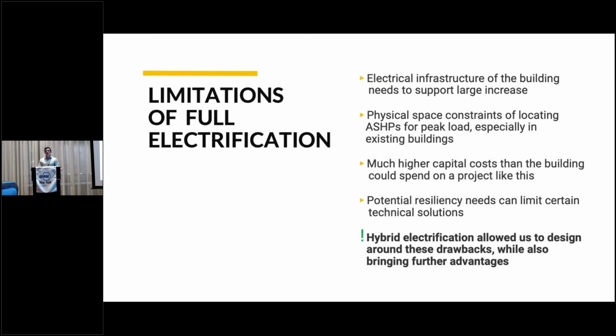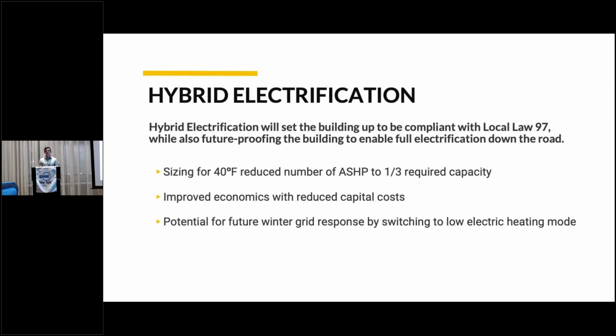So when we were looking at a hybrid electrification project, we realized that not only was it avoiding some of these pitfalls, but it was actually bringing additional advantages. Just to recap, the hybrid electrification project that we settled on was sizing our heat pump for 40 degrees Fahrenheit, which reduced the capacity that we needed to 1/3 of what a full electrification project was. It had greatly improved economics, and it also allowed us to set the stage for resiliency if the grid goes down, but an interesting thing to think of is as we move forward towards full electrification.